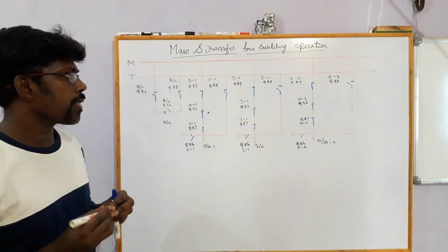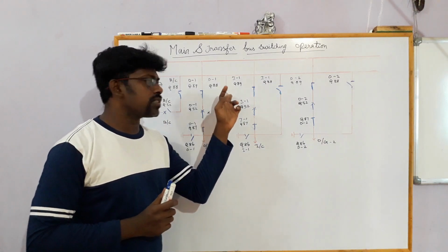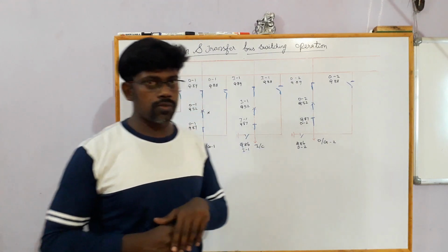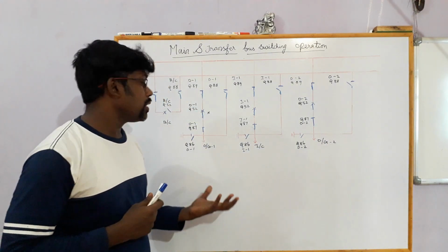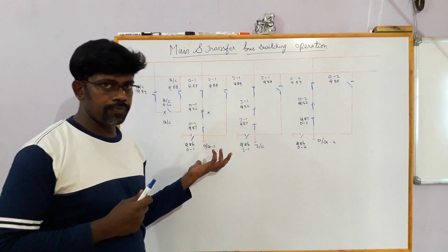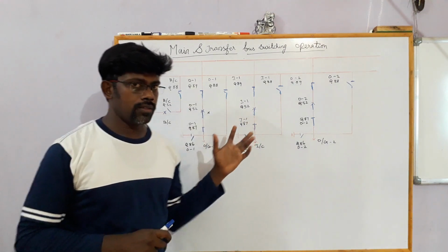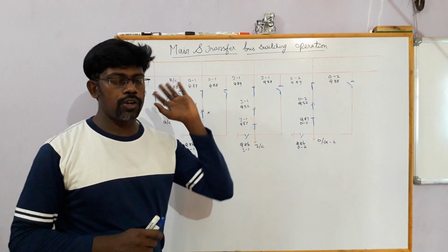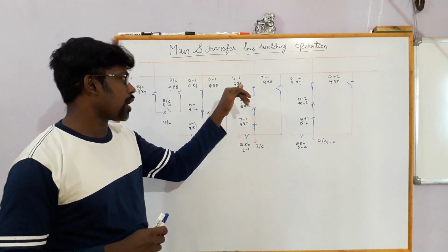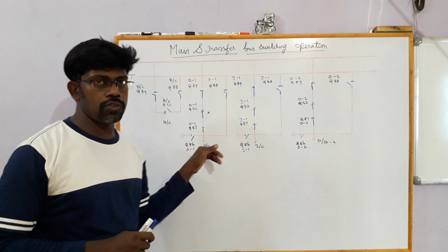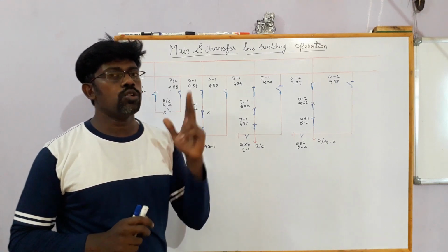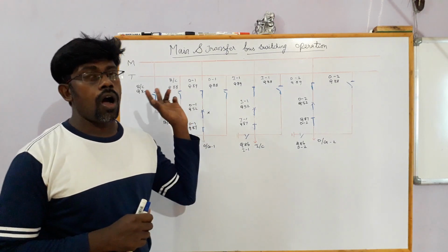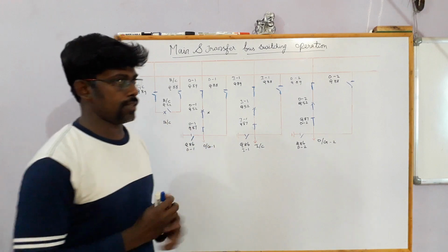We have some procedure. There are two types of switching this isolator. One is on-load transfer, another one is off-load transfer. Now what is on-load transfer? When this outgoing has a load, without interruption of power is on-load. Off-load is where we cut off this outgoing load, connect this isolator, and then give the load. For that we have two methods of closing. First we will see the on-load transfer, that is without power interruption.